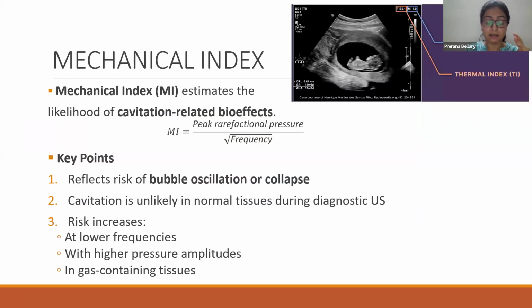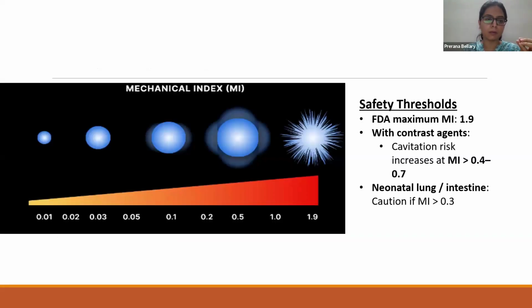Similarly, mechanical index indicates the likelihood of cavitation-related bioeffects. So it reflects bubble oscillation or collapse. Any bubbles that form inside blood vessels especially would be dangerous, and they can go on increasing and then rupture. That's because of the shear stress that the waves are producing on small structures. Cavitation is unlikely, and the risk of mechanical damage increases at lower frequency with a higher pressure amplitude and in gas-containing tissue. So it's a small bubble, it goes on increasing, and then it can also explode at an index of more than 1.9. So the maximum allowable according to the FDA is 1.9. With contrast agents, the threshold is lower, at 0.4 to 0.7. And if we are scanning the neonatal lung or intestine, it should not be more than 0.3.